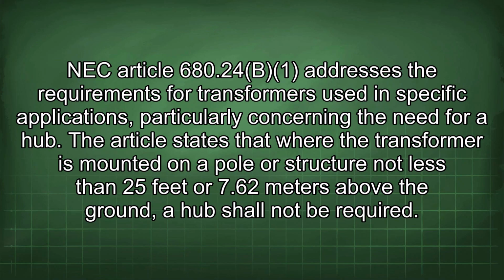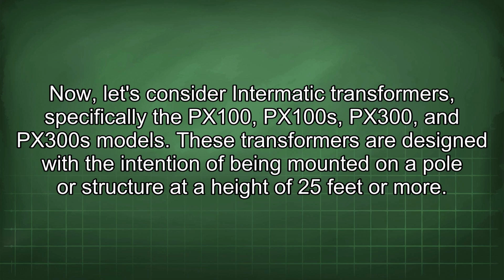NEC Article 680.24(B)(1) addresses the requirements for transformers used in specific applications, particularly concerning the need for a hub. The article states that where the transformer is mounted on a pole or structure not less than 25 feet or 7.62 meters above the ground, a hub shall not be required. Now, let's consider Intermatic transformers, specifically the PX100, PX100s, PX300 and PX300s models.